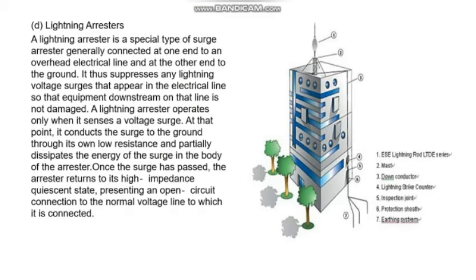Fourth example is the lightning arresters. A lightning arrestor is a special type of surge arrestor, generally connected at one end to an overhead electrical line and at the other end to the ground. It thus suppresses any lightning voltage surges that appear in the electrical line so that the equipment downstream on that line is not damaged. A lightning arrestor operates only when it senses a voltage surge.